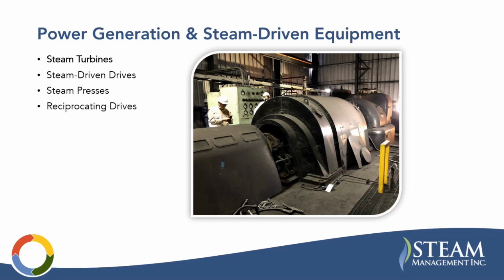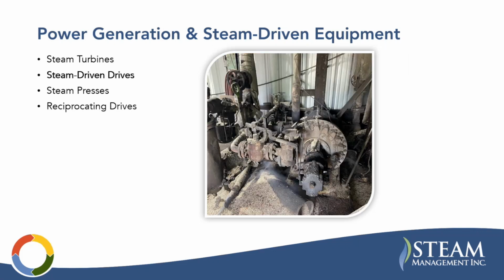And now on to power generation. So obviously steam is used in steam turbines to generate power, whether those are turbo alternators or turbo expanders. They're steam driven drives, like you see here. This is a boiler feed water pump actually that has a turbine attached to it, a steam turbine attached to it, just for the mechanical drive of the pump.